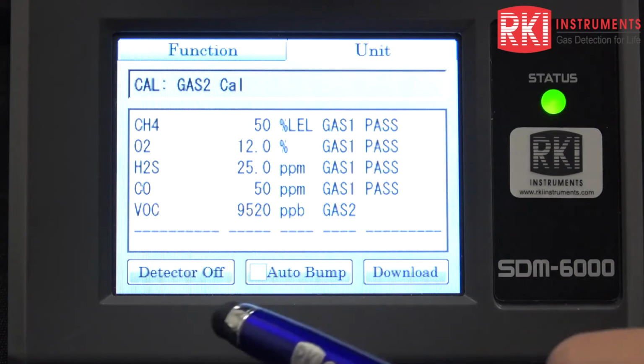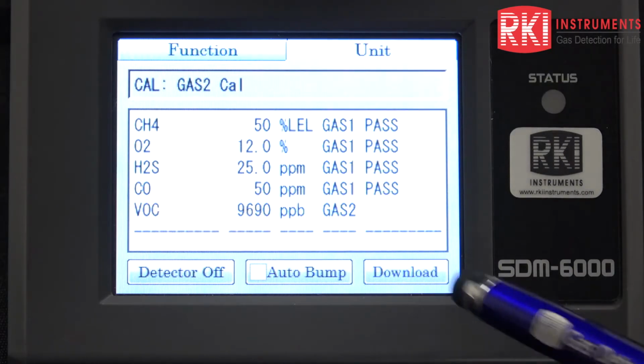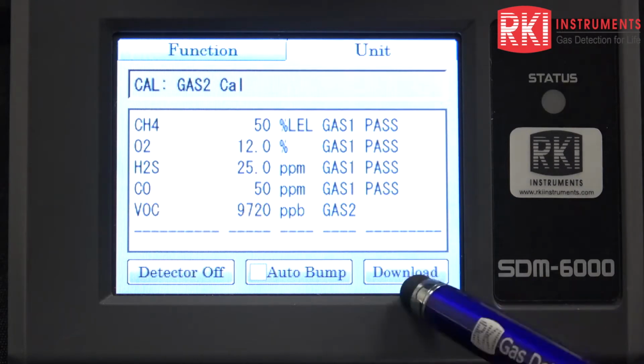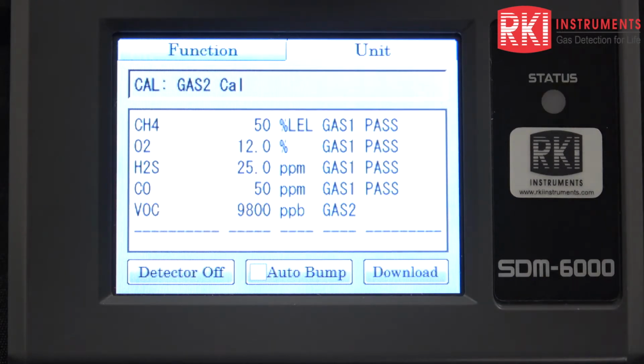One thing I'd want to mention is the auto bump and the download. The download would allow you to download whatever data is on your GX 6000 meter onto the SD card of the SDM 6000. And you also have an auto bump. That way, when you plug your 6000 meter into the calibration station, it's going to automatically do a bump test. And detector off, that's just to turn off the detector.